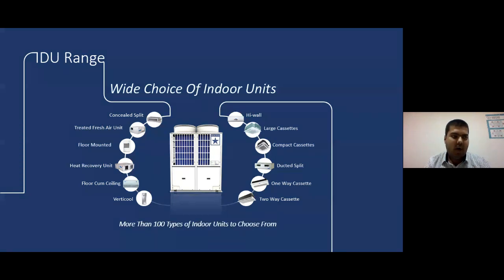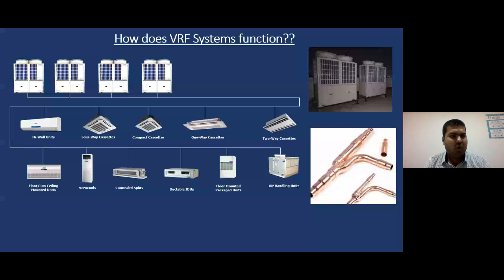This is basically an outdoor unit of, say, 28 HP, which is close to 22 tons. And the white line that you can see is basically a copper piping which is flowing through all the areas. I can install high wall, four-way cassettes, one-way cassettes, and two-way cassette units. So what happens is, suppose a person sitting in a room with a two-way cassette sets the temperature to 24 degrees Celsius, it would give the signal to the outdoor unit. Only that much refrigerant will flow through this entire pipeline, and only this machine will work. So that is the beauty of VRF, that you can handle each required temperature in each separate room.